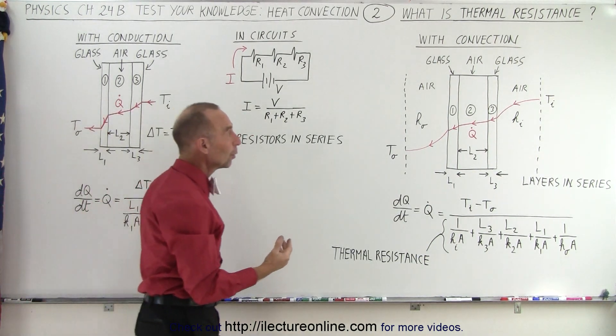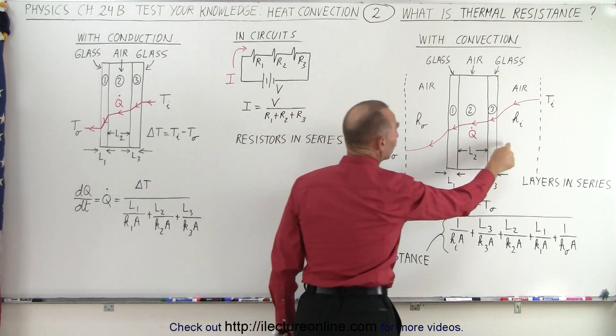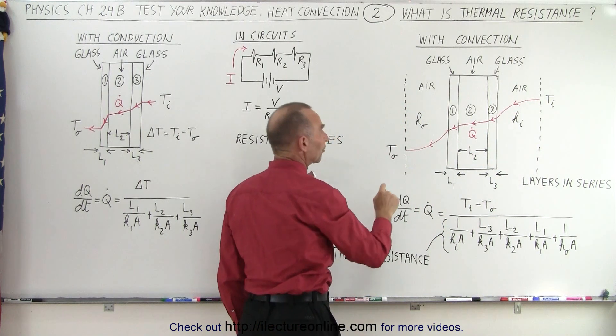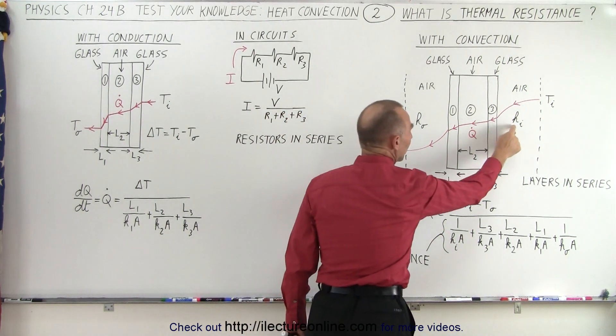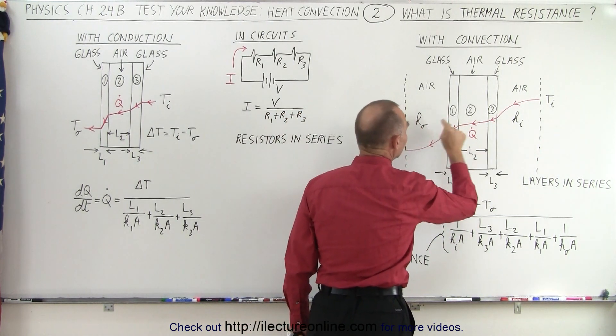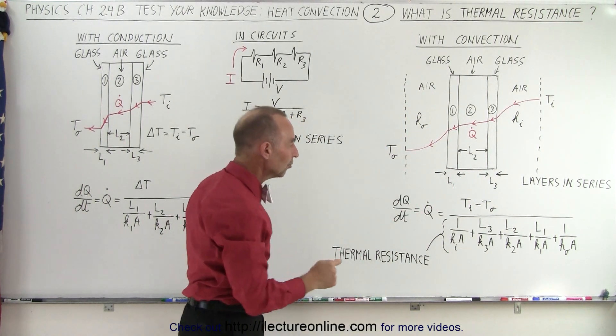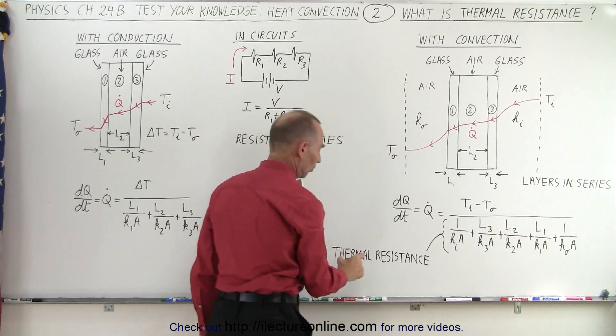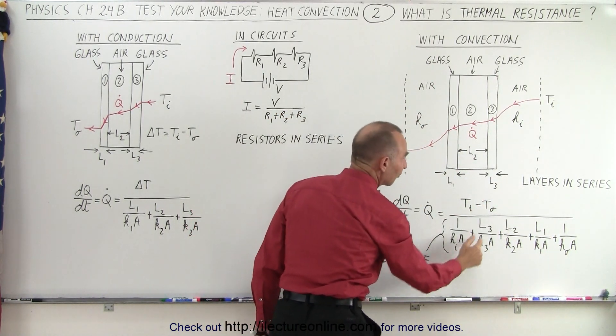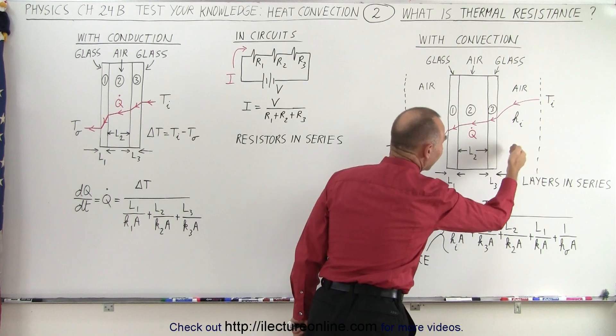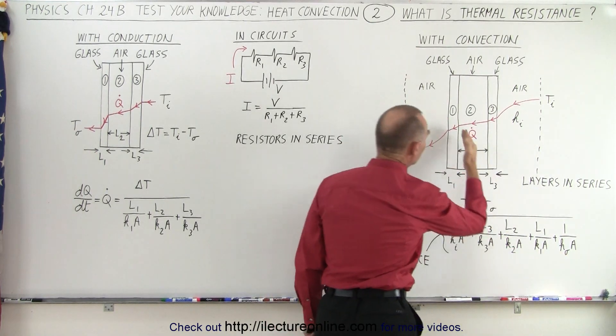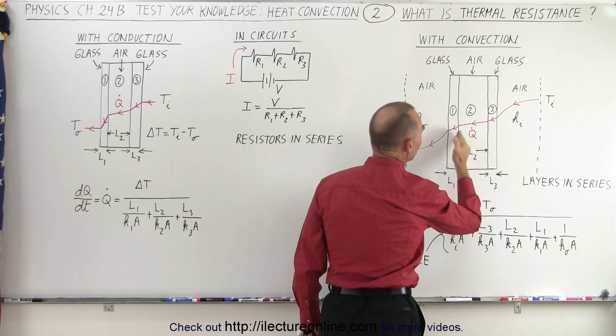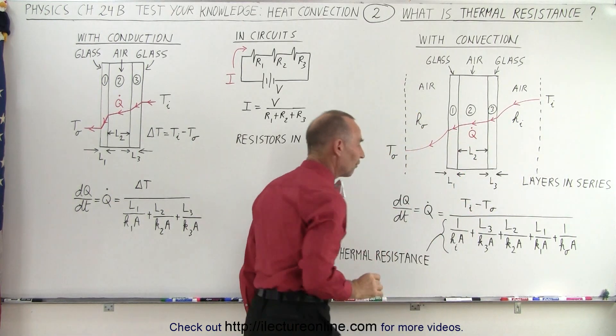We also need to take into account the resistance to heat flow due to convection on either side of the window. These depend upon the transfer coefficients on the inside and the outside relative to the glass. Notice that this simply adds two more resistance terms — thermal resistance due to convection on the inside and on the outside — while still keeping the other three terms associated with the two layers of glass and the layer of air in between.